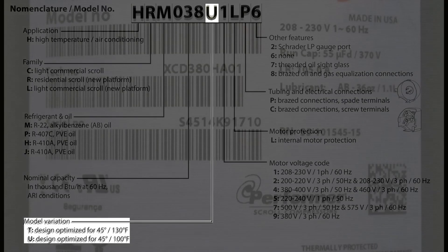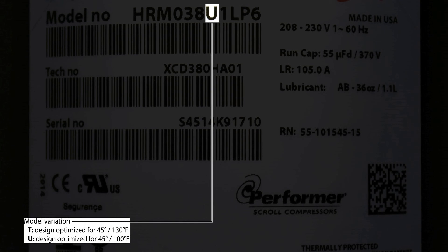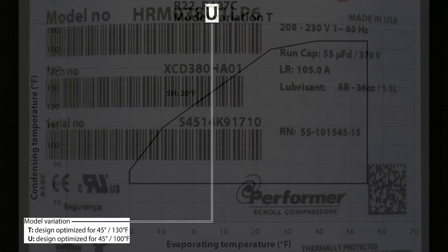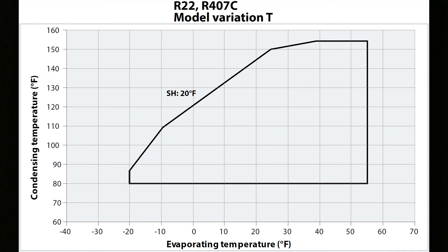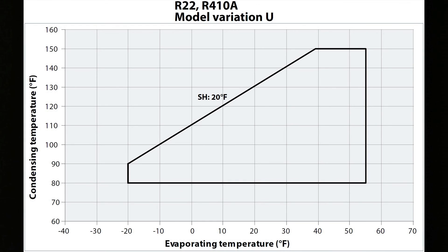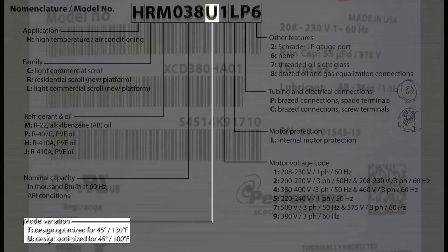The seventh digit signifies the model variation, which represents design conditions under which the performance of the compressor is optimized. Model variations with T are optimized with an evaporator temperature of 45 degrees Fahrenheit and a condensing temperature of 130 degrees Fahrenheit, while model variations with U are optimized with an evaporator temperature of 45 degrees Fahrenheit and a condensing temperature of 100 degrees Fahrenheit.